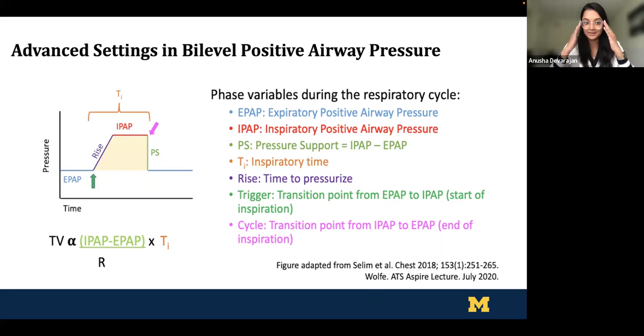So this is where I'm going to be focusing a little bit more time so that when I get to my slide on asynchronies, hopefully with the concept of what cycle is, what trigger is, which of these are actually getting activated in a spontaneous versus a machine-delivered breath, it makes it a little bit clearer to understand asynchronies. And I wanted to reiterate that the reason why I'm bringing this up is because we encounter so many titrations where there are challenges to get a good setting because they are super off, and the patient and the ventilator are just not in sync with one another, and that's why it becomes important.